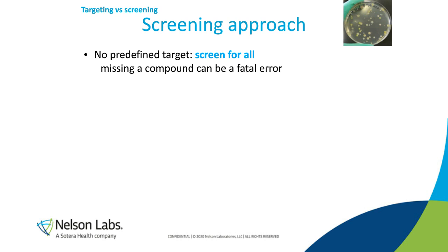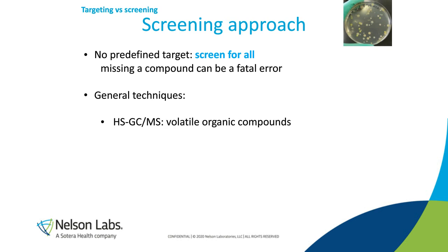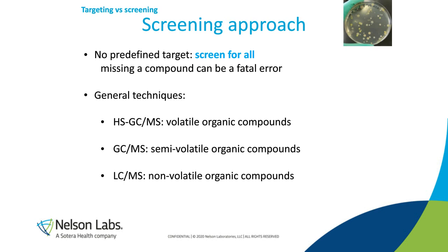So our net could be not close enough, and some of these CMRs could be leaching. We could be not knowing what they look like, and so they could be lost by not being identified as a CMR. But we would go through this process very similar to what Matt talked about yesterday, just using some general screening techniques that are found in ISO 10993-18 to try to apply screening for these CMRs. So those are the two techniques you could go through, and honestly, you're probably going to have to use a combination of both of them to really understand the full potential of your CMRs in your device.